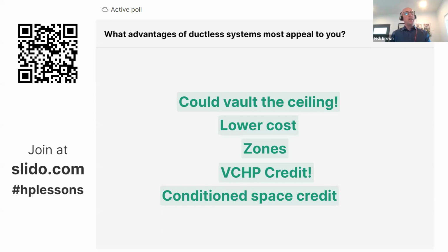I know when I did my ADU, I used a ductless mini split, two indoor units, a single outdoor unit, a ton and a half, I think, 18,000 BTUs was enough for the whole 576 square foot unit. And we were able to vault the ceiling because we didn't need the attic for the mechanical system. Been working great.